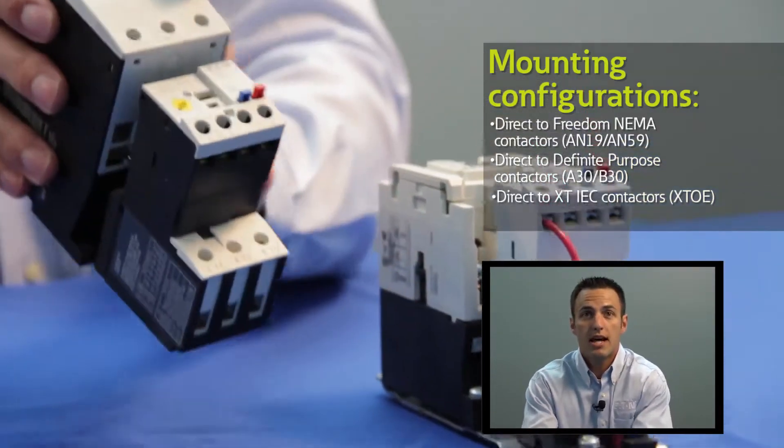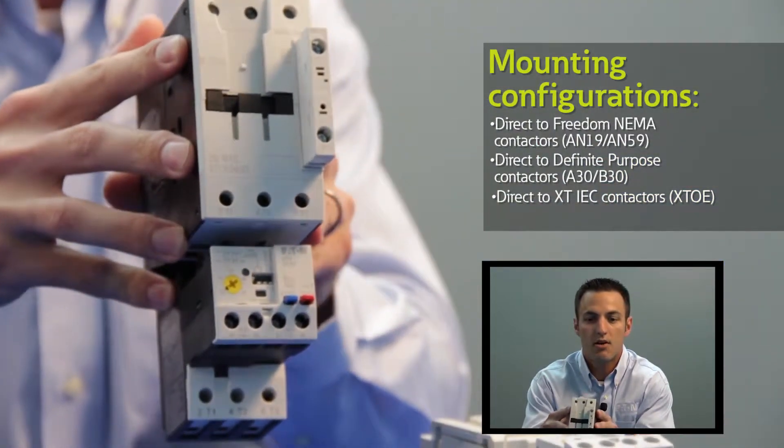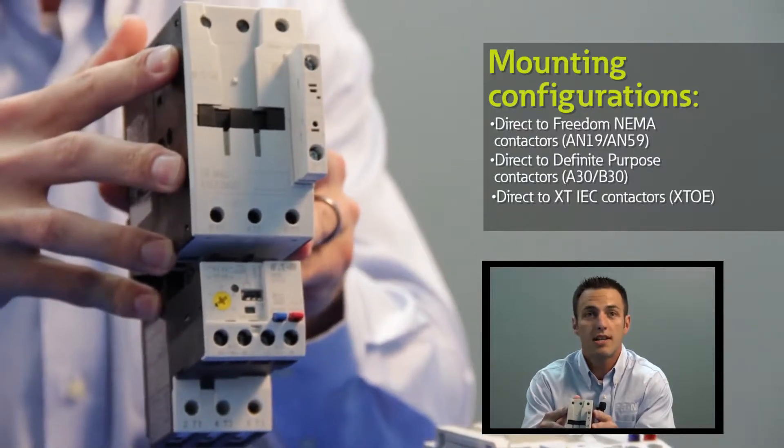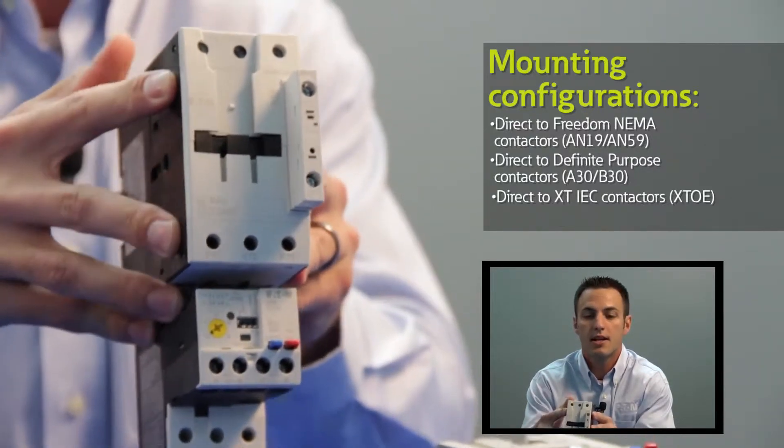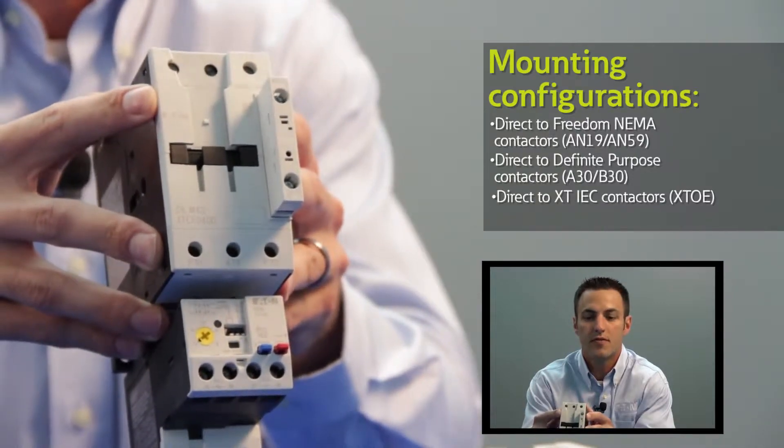Direct mounted to the XT IEC contactors up to 175 amps, we call this the XTOE. Above 175 amps we also utilize an external current transformer solution for applications up to 1500 amps.